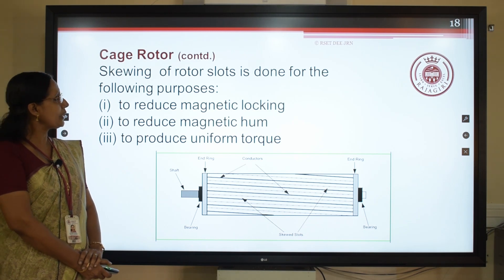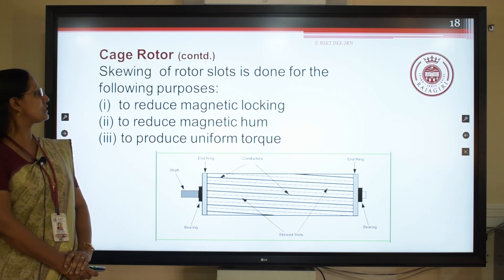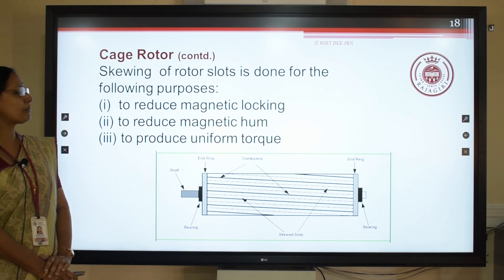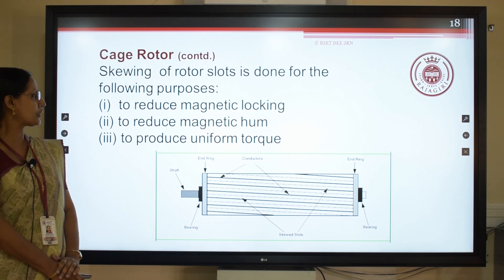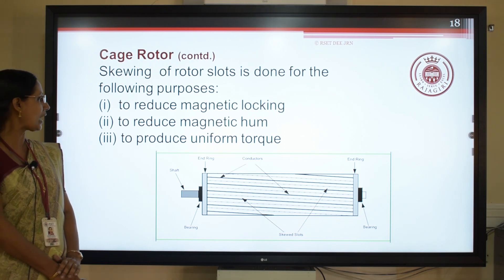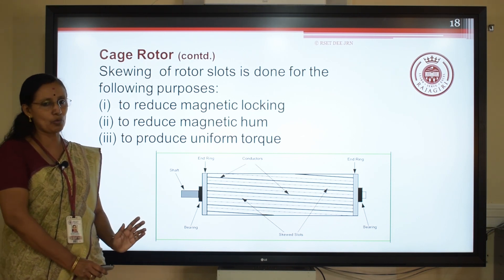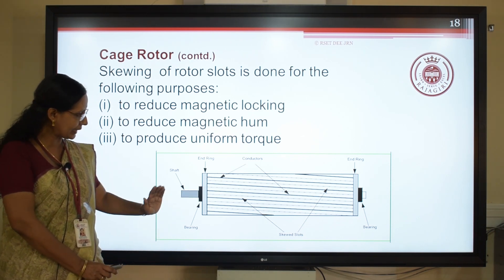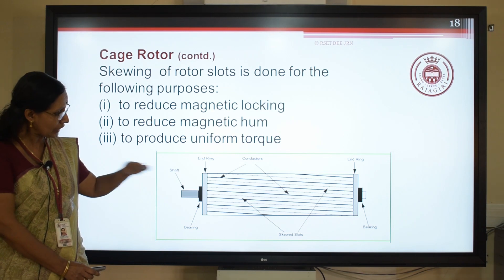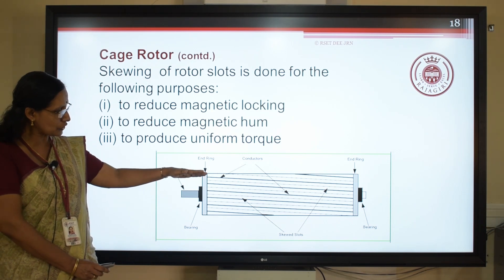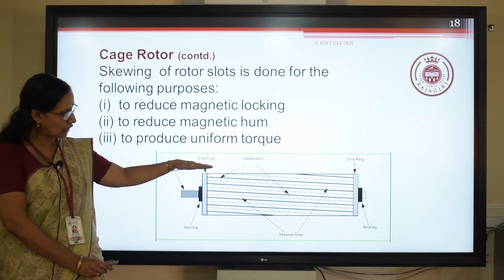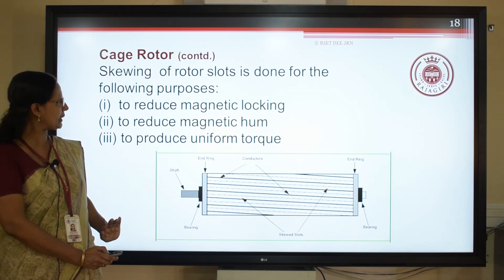Skewing of the rotor slots is done for the following purposes: to reduce magnetic locking, to reduce magnetic hum, and it provides a uniform torque. As you can see in the diagram, the slots are cut not parallel to the shaft but at an inclined angle of 15 degrees.